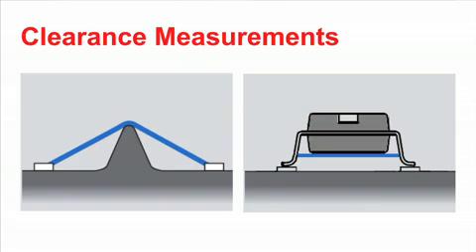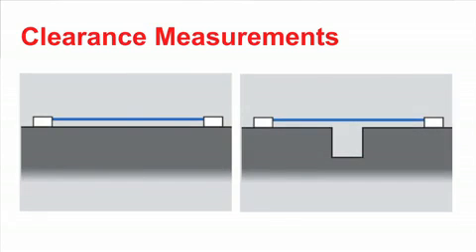These are terms that describe the distance between conductors in a high voltage isolation barrier. Clearance is the shortest distance through air between two uninsulated conductors. These diagrams show different examples of how to measure clearance distance. Having adequate clearance for the voltage level and environment you are designing for will prevent an arc over — when air becomes ionized and current begins to flow, shorting across the isolation barrier by arcing through the air.